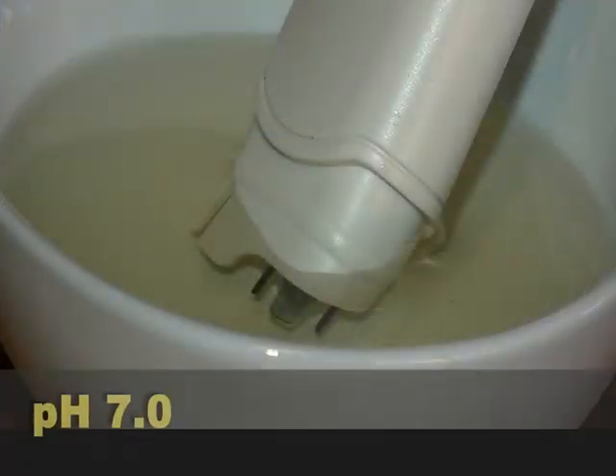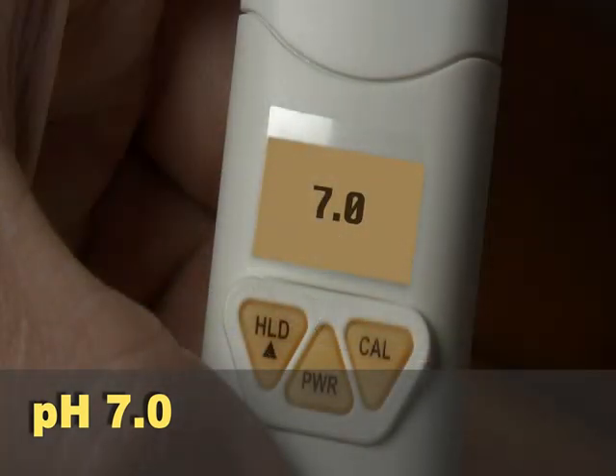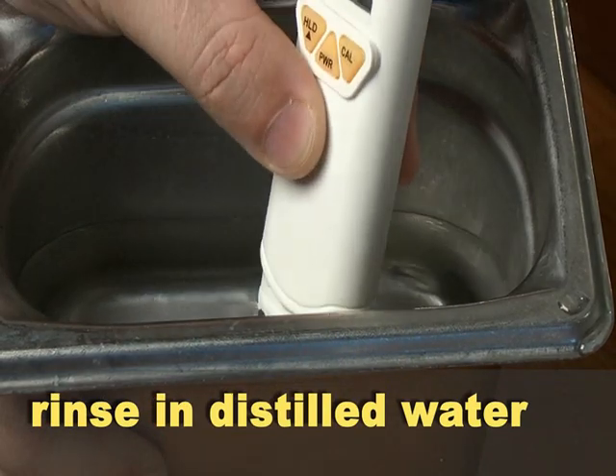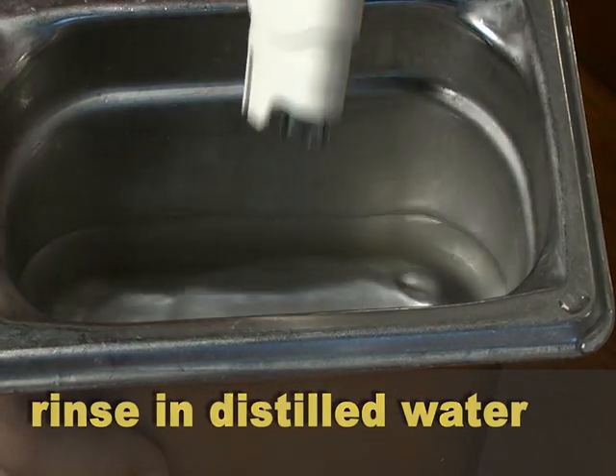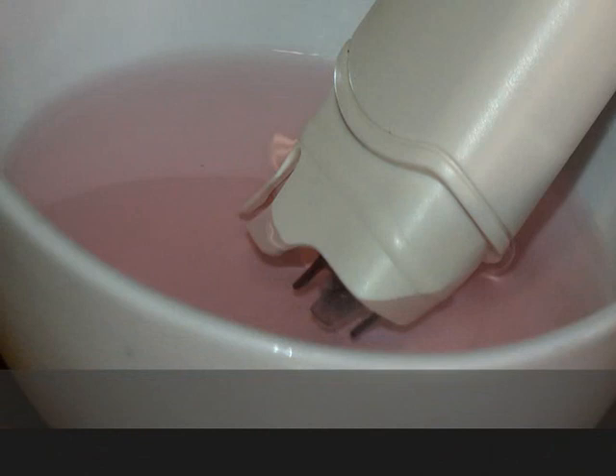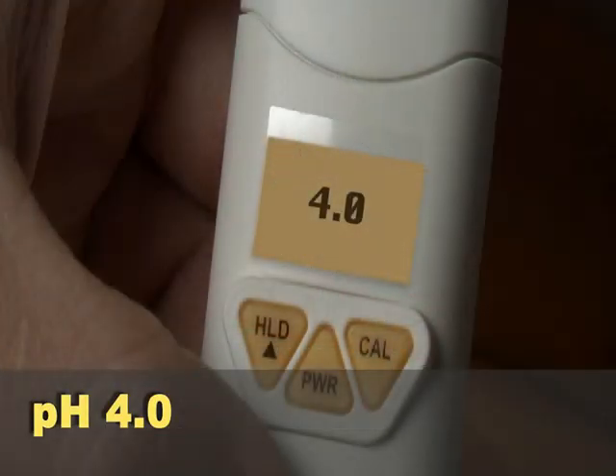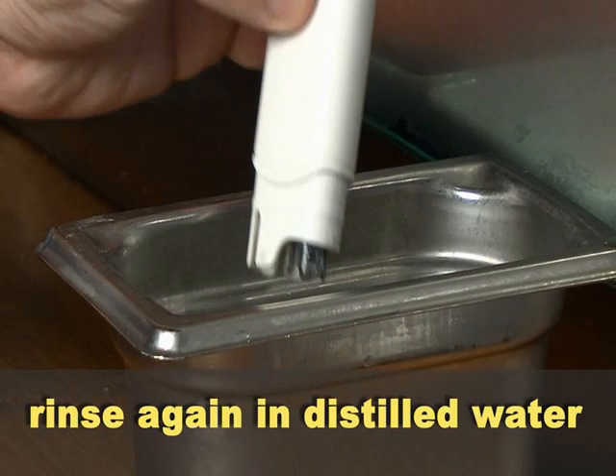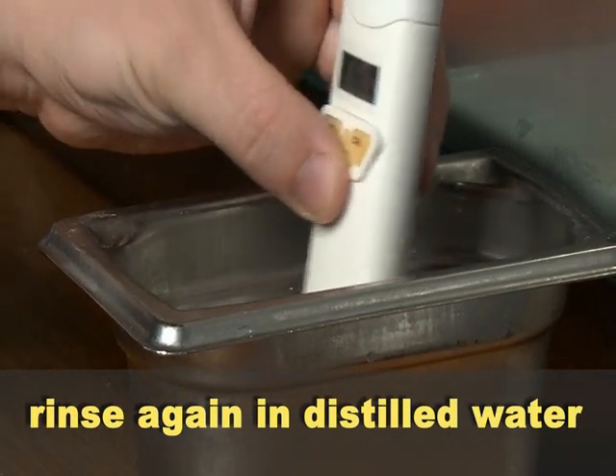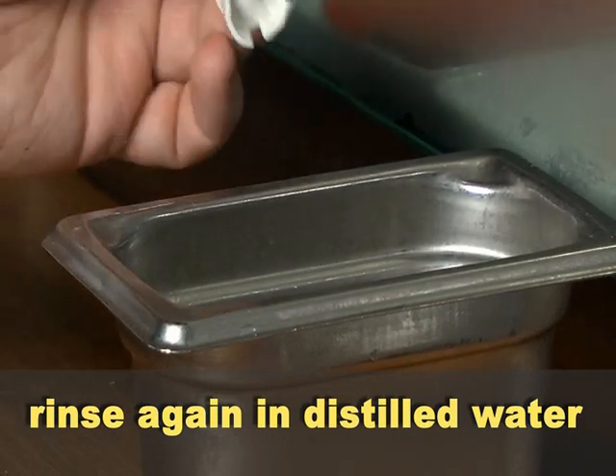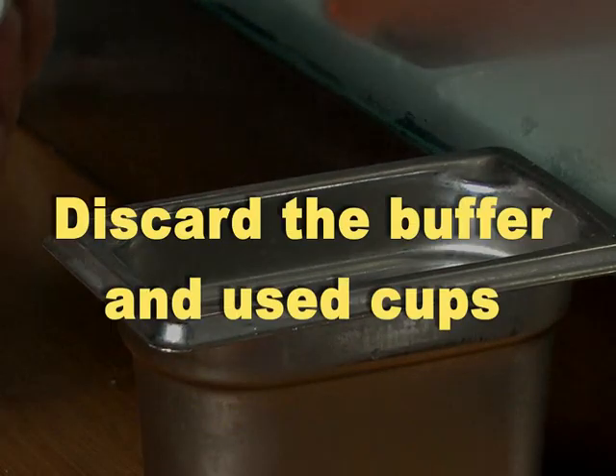Immerse the pH electrode into the pH 7.0 solution following the manufacturer's instruction. Rinse the pH electrode in the distilled water container. Now immerse pH electrode into the pH 4.0 buffer, again following the manufacturer's instructions. Rinse the electrode in the distilled water. Your pH meter is now calibrated. Discard the buffer and used plastic cups.